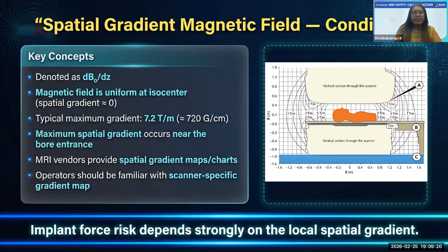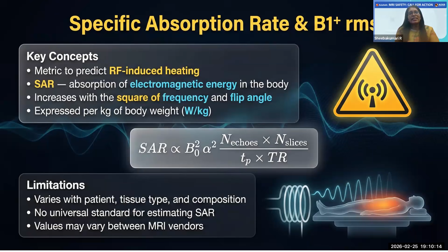Coming to the SAR, the specific absorption rate, that is the amount of RF energy absorbed by the patient's body. It is calculated according to the patient's body weight and expressed as watt per kg. It is a measure of RF energy absorbed by the body, and it varies with the patient's tissue type and composition. So it is not an accurate measure, and it is not a universal standard. It doesn't guarantee against RF heating, but we can use it as guidance. The SAR calculation is directly proportional to the square of the frequency, flip angle, number of echoes, and number of slices, and inversely proportional to the pulse duration and TR.